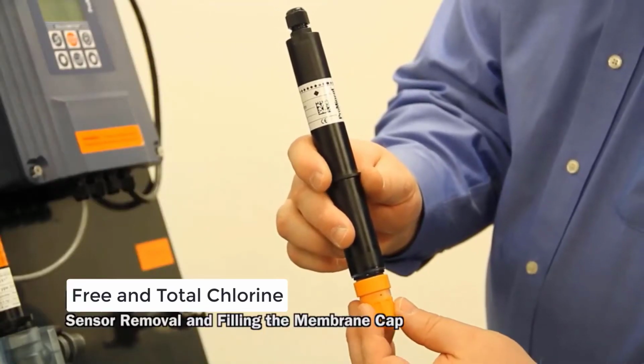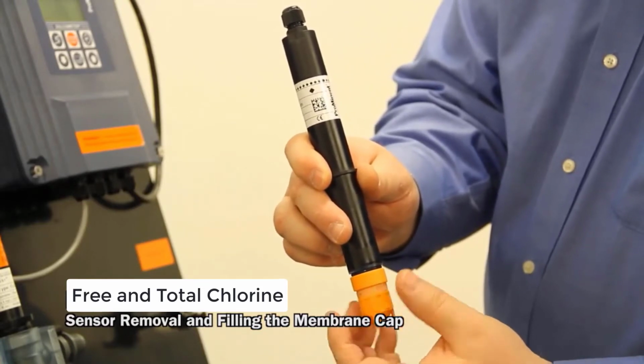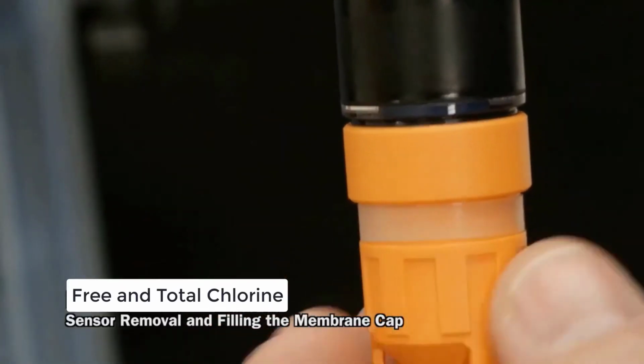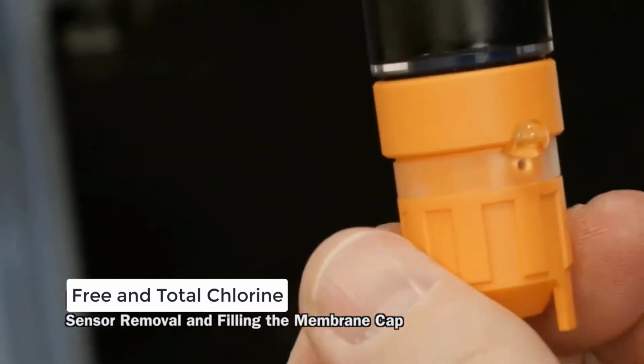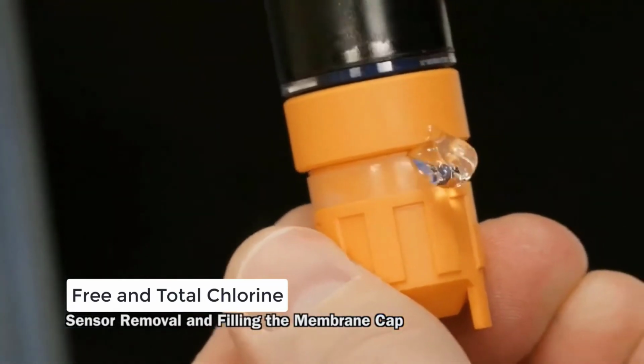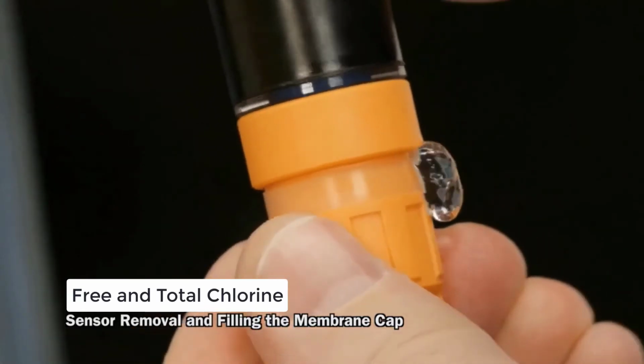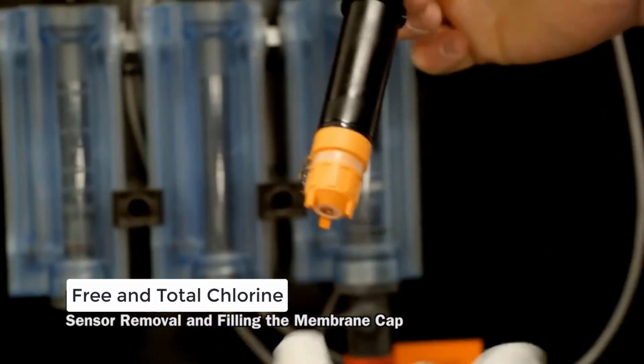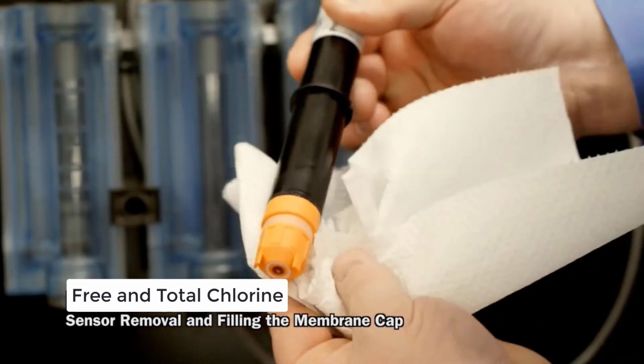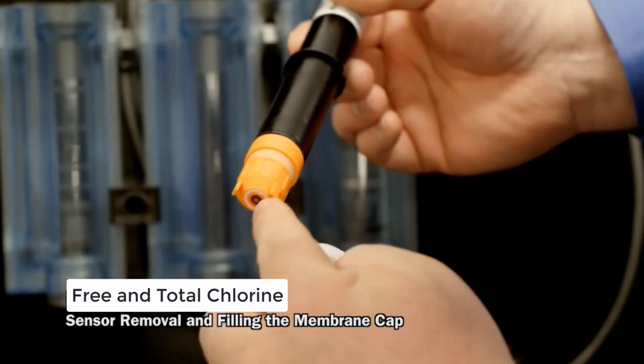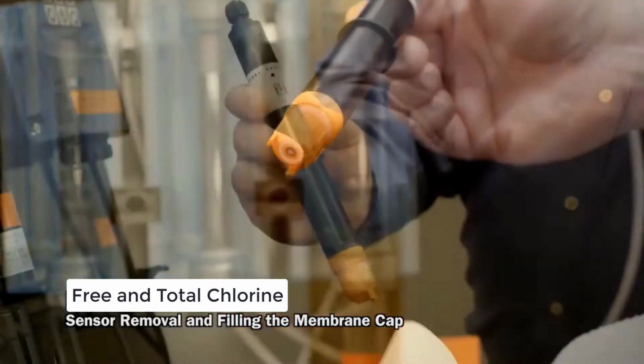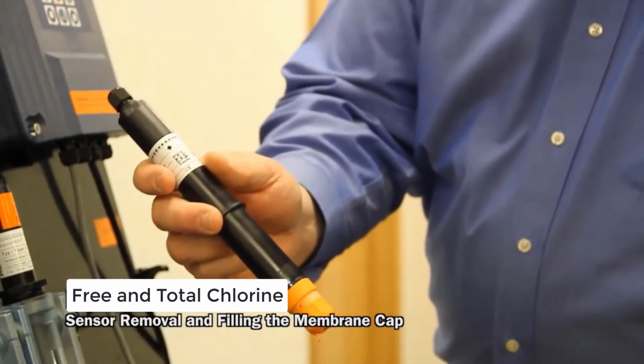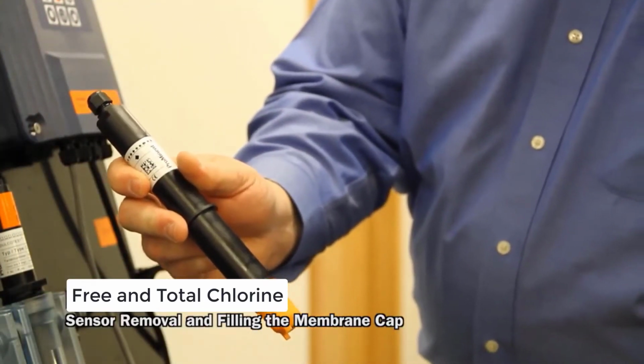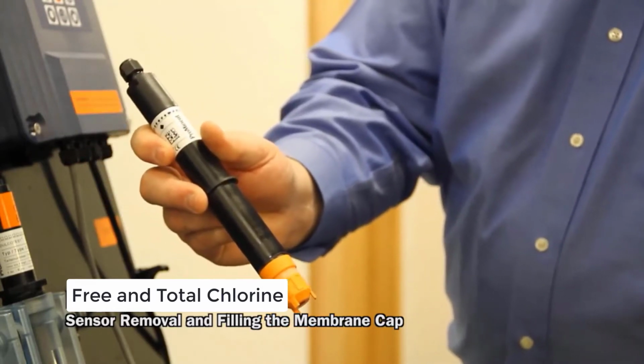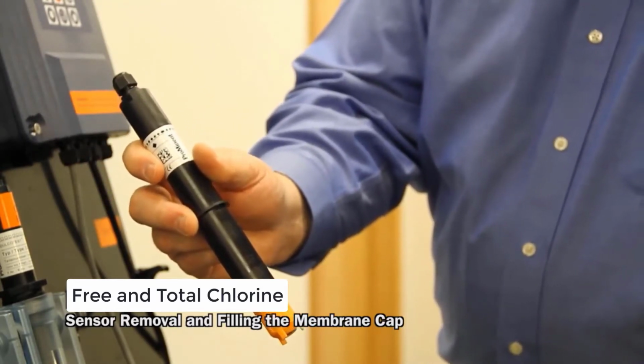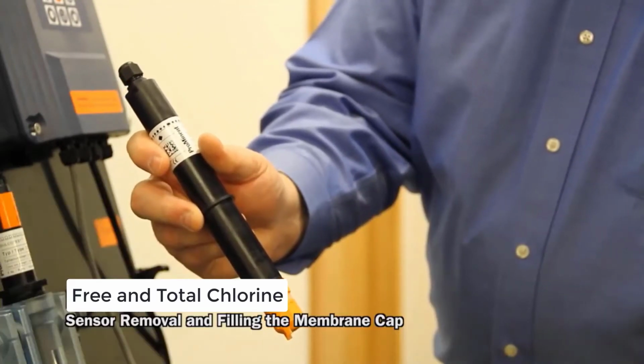We'll now thread that sensor back on. You'll see that the electrolyte will come out. Then we will want to wipe that electrolyte. Never wipe across the membrane itself. Now we can put this sensor into flow. It tends that the electrolytes take a little bit longer to energize, so you'll have to wait a little bit longer to do your calibration.